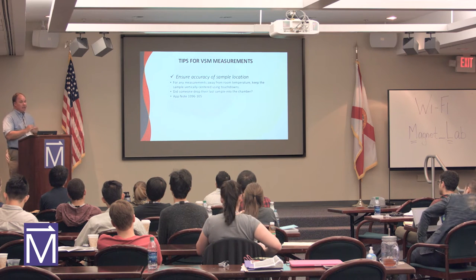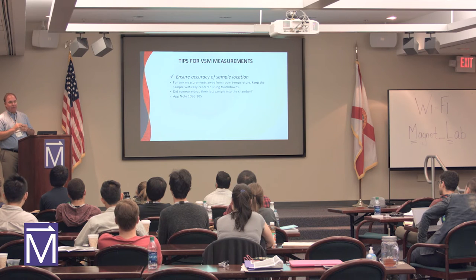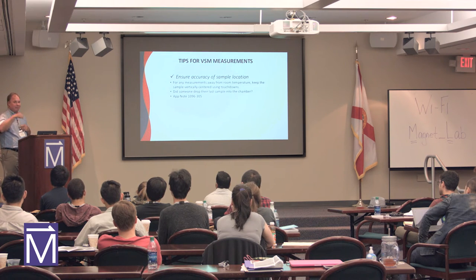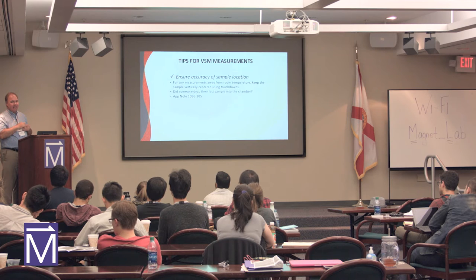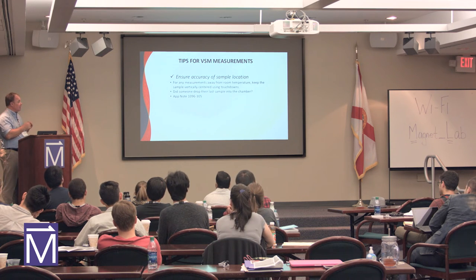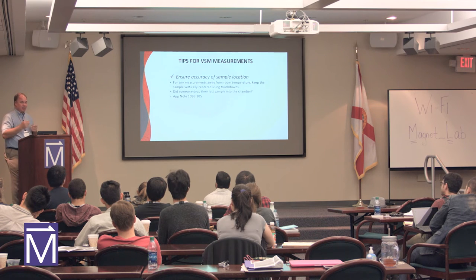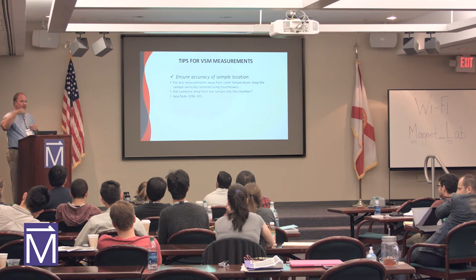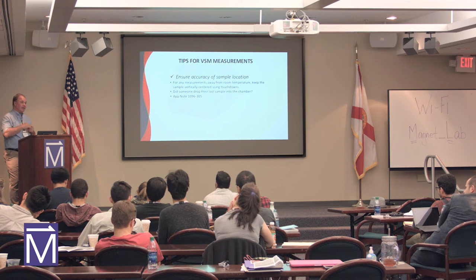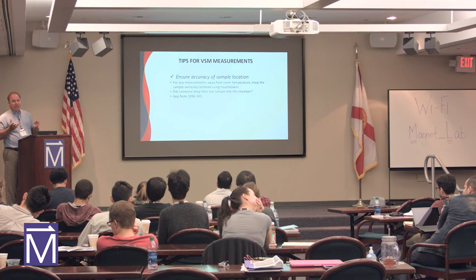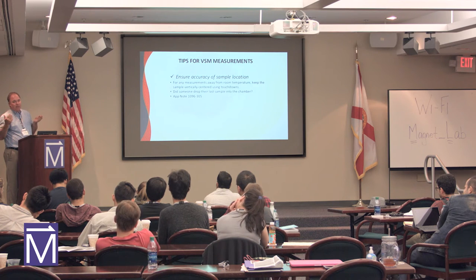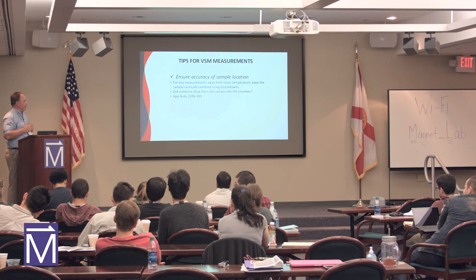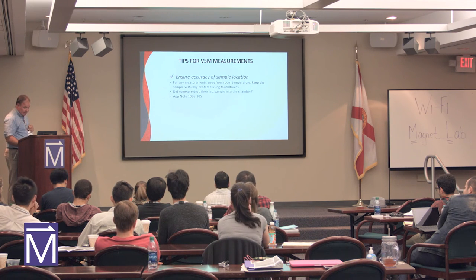A common thing is that our service guys will go in and find that somebody dropped a sample. Oh, the VSM doesn't work. Some people make a measurement, the sample falls off into the bottom, it does the touchdown, and things are off spatially because it's hitting the last guy's sample. I was asking the service manager what the common thing is. He said this is very common, because people drop things in there, and then they leave and don't tell the next person, and then people are scratching their heads while the instrument doesn't work. So if you drop something in, tell somebody. Don't just leave it in the sample space. If you tell somebody, people are pretty nice. Otherwise you're going to have to go fishing, but it's better to do that than have bad data. And there are a couple of application notes on these things.